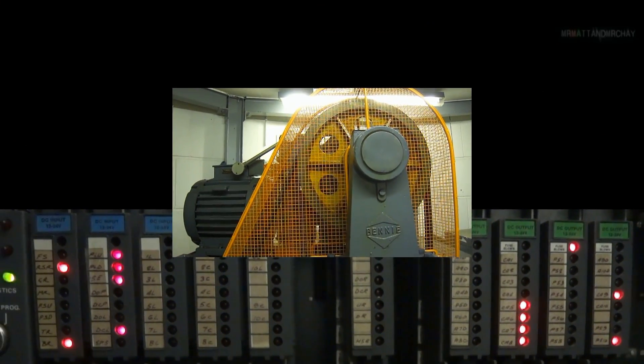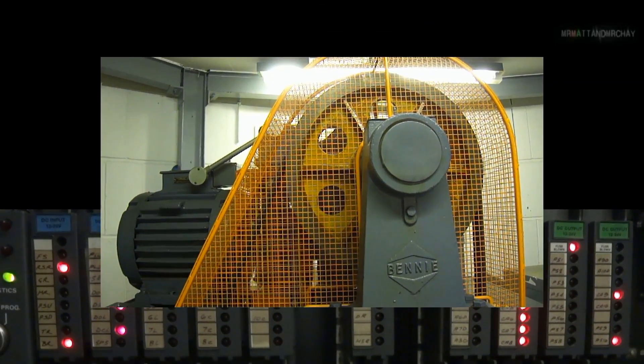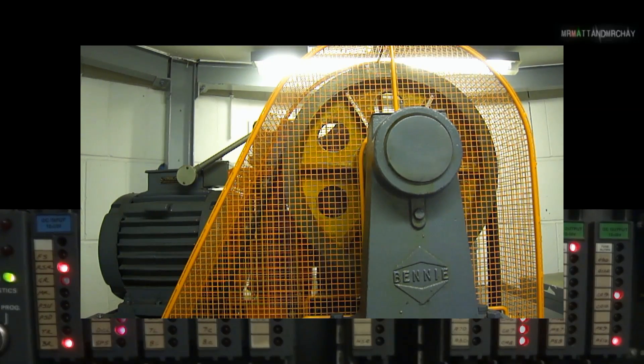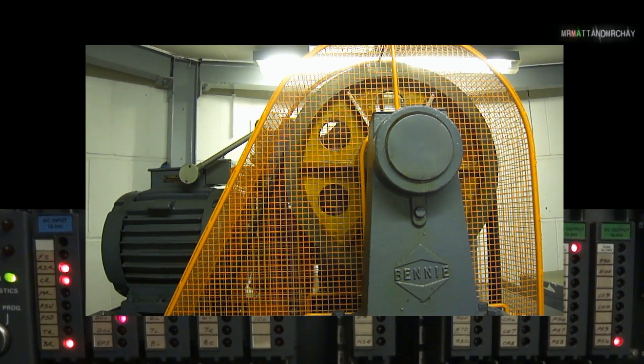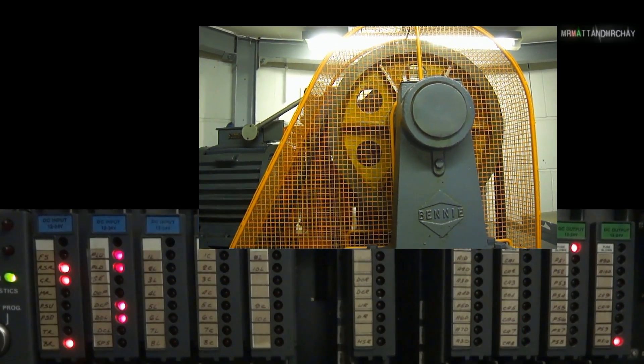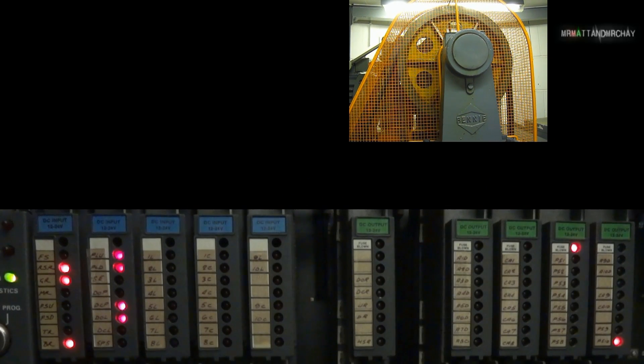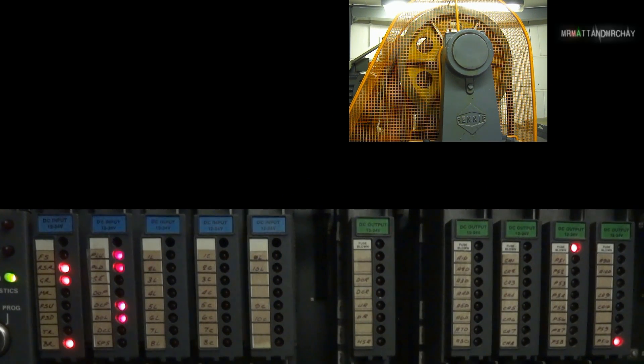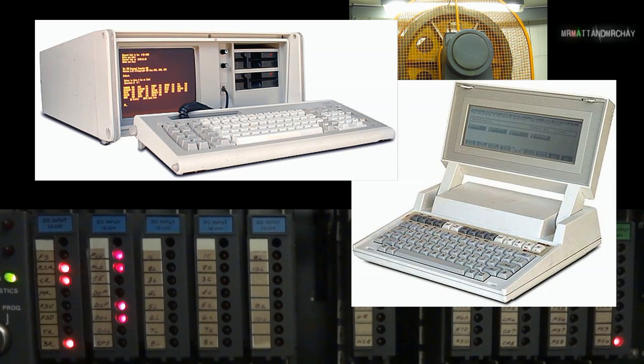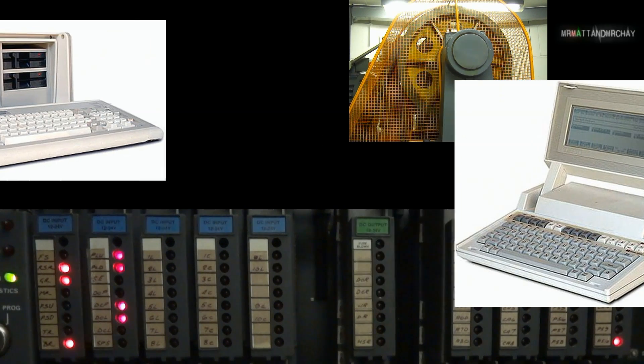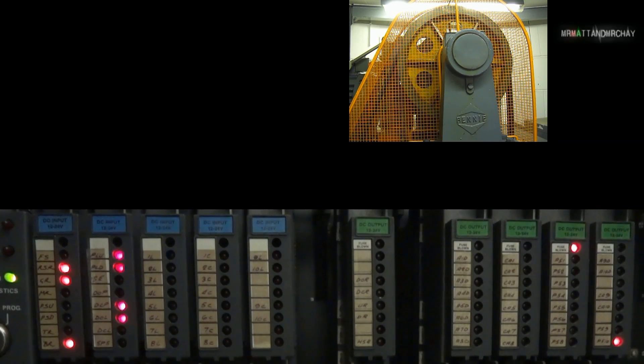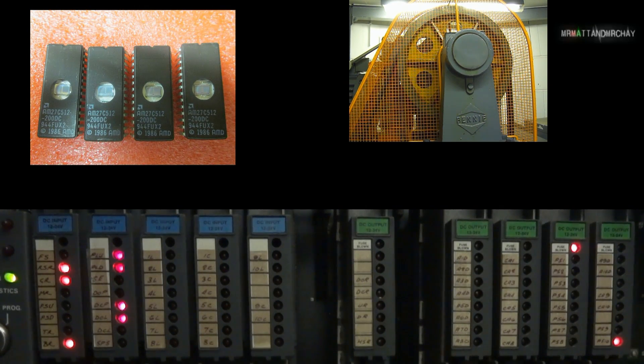The PLC does nothing without being programmed. The programming would have been developed and written by Bennie. This controller was installed mid-1980s, so I'm guessing this would have been done in a workshop, as laptops from the mid-1980s looked like this. The programming could have been written on a chip called an EEPROM, which is then plugged into the processor card.